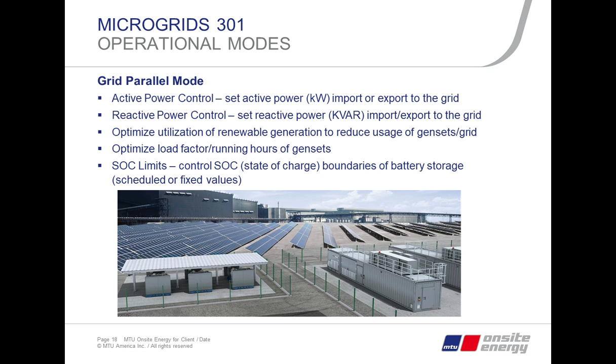That's right, and as we'll show later, it can really make sense to use gensets of different sizes to optimize the load factor, because we don't want to run a genset at 20 or 30% load if we can avoid it. We want to run it at a high load factor, where it's most optimal in terms of fuel efficiency and maintenance.